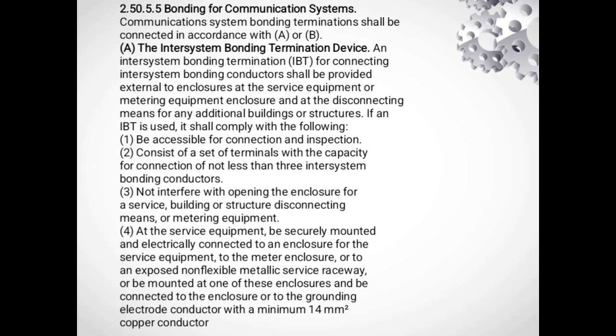2.50.5.5 Bonding for communication systems. Communication system bonding termination shall be connected in accordance with A or B. A. The inter-system bonding termination device. An inter-system bonding termination, IBT, for connecting inter-system bonding conductors shall be provided external to enclosures at the service equipment or metering equipment enclosure and at the disconnecting means for any additional building or structures. If an IBT is used, it shall comply with the following.